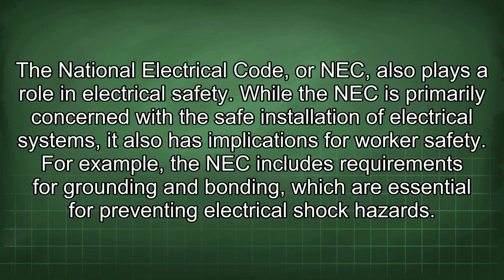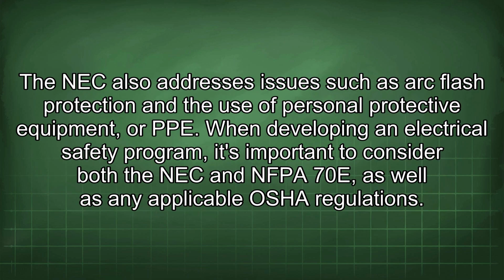The National Electrical Code, or NEC, also plays a role in electrical safety. While the NEC is primarily concerned with the safe installation of electrical systems, it also has implications for worker safety. For example, the NEC includes requirements for grounding and bonding, which are essential for preventing electrical shock hazards. The NEC also addresses issues such as arc flash protection and the use of personal protective equipment, or PPE. When developing an electrical safety program, it's important to consider both the NEC and NFPA 70E, as well as any applicable OSHA regulations.